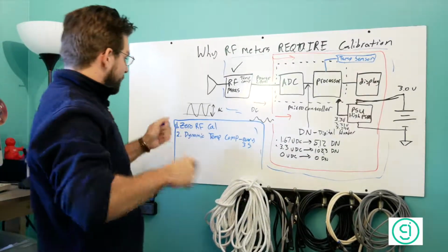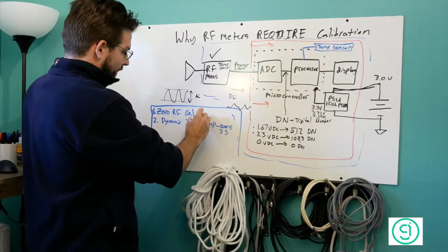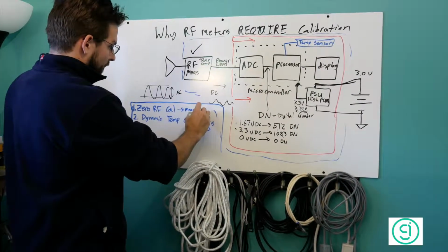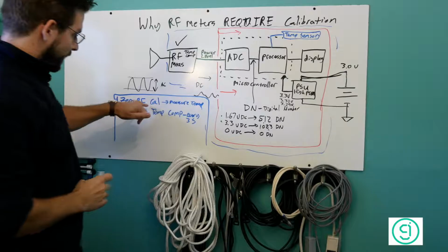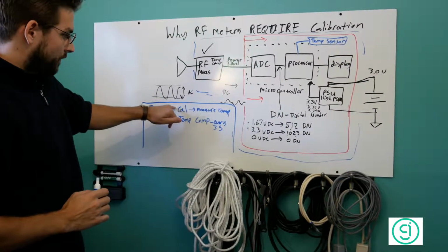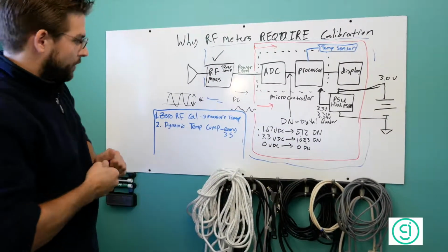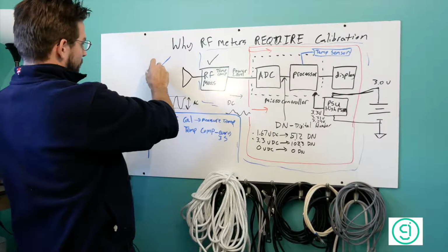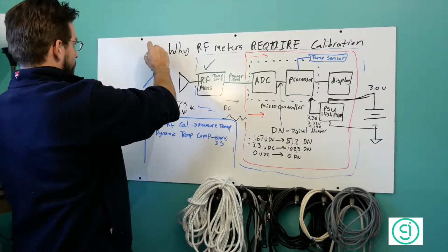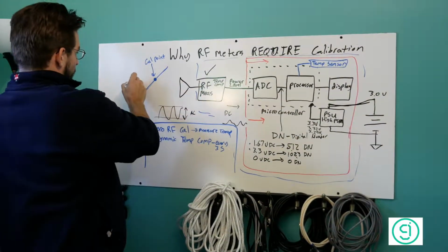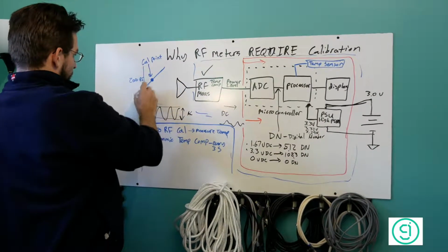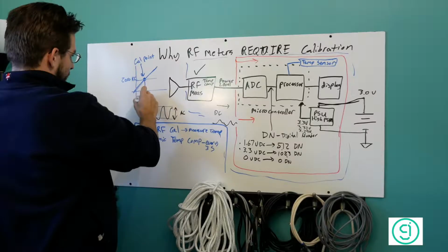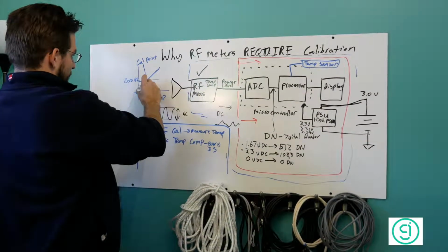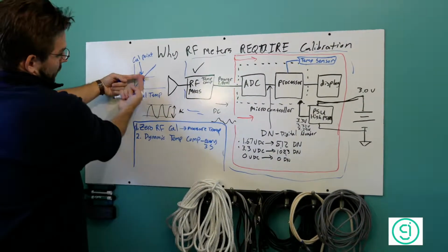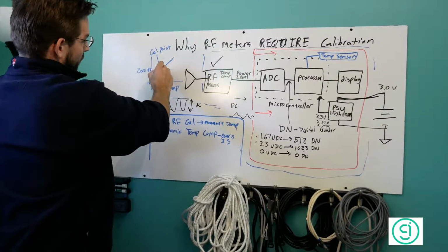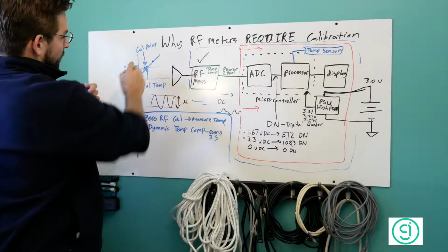The other thing that we do, which is actually up here in the 0 RF cal, we measure temperature while we are doing our 0 RF cal at the factory here. So this value is referenced to a reference temperature, and that's what pins us down. Here's our temperature compensation curve. This would be our calibration point, cal point. So we know that 0 RF on this axis is here, and we know that this is the cal temp here. 0 RF calibration temperature puts us on this line. Then if our meter heats up, we shift to a point up here. If our meter cools off, we shift to a point down there.